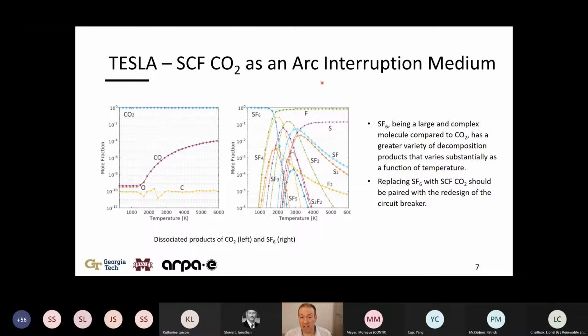Here in the center, I have a diagram of what happened to SF6, where you get fluorine gas, you get solid sulfur when it cools down, and you get all sorts of other decomposition products. And this doesn't even include what would happen if there's any moisture in the system or any other contamination, maybe small amounts of nitrogen or oxygen, trace amounts of oxygen or so that are inside the circuit breaker.